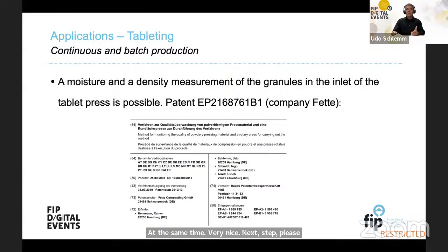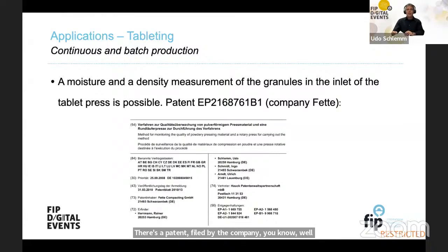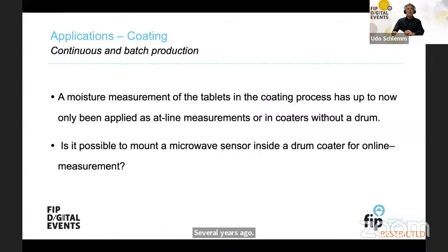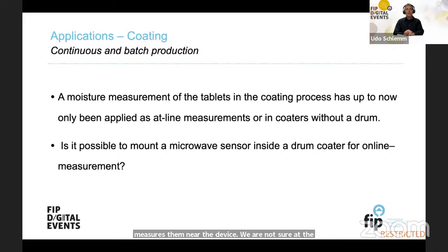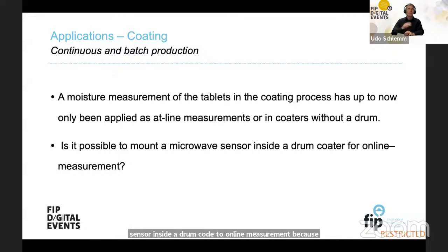Coming to the next step of production — tableting — moisture and density measurement of the granules can be done at the inlet of the tablet press. There's a patent filed by the company FETTE, a well-known producer of tableting machines, filed with inventors from both companies. In coating, we have only experience with at-line measurements, taking single tablets out of the coating process and measuring them near the device. We are not sure at the moment if it is possible to mount a microwave sensor inside a drum coater for online measurement, because the microwave sensor may not be sprayed with a coating solvent.